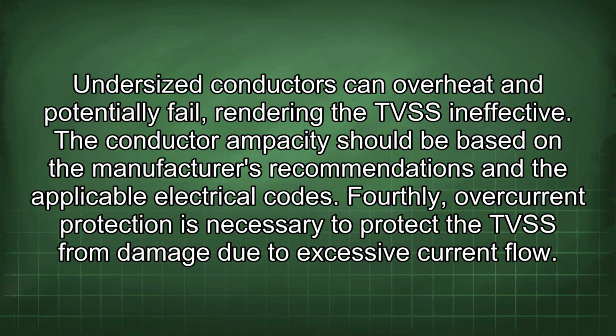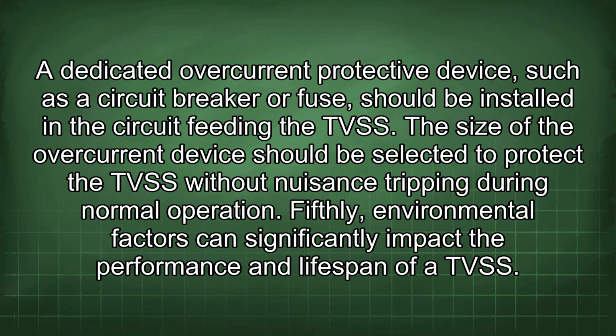Fourthly, overcurrent protection is necessary to protect the TVSS from damage due to excessive current flow. A dedicated overcurrent protective device, such as a circuit breaker or fuse, should be installed in the circuit feeding the TVSS. The size of the overcurrent device should be selected to protect the TVSS without nuisance tripping during normal operation.